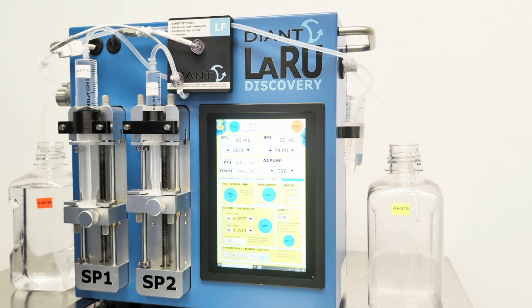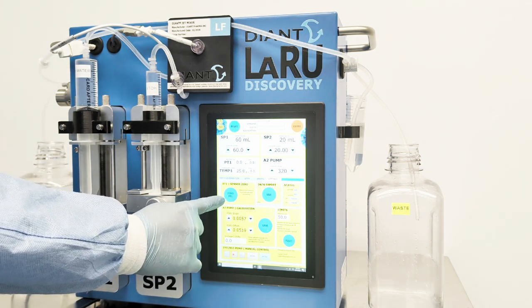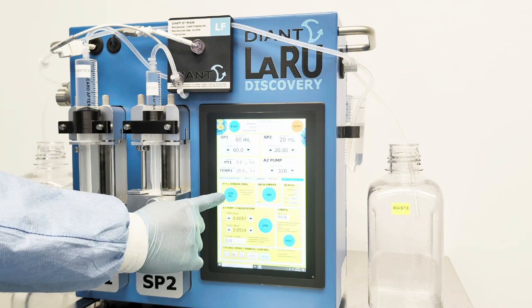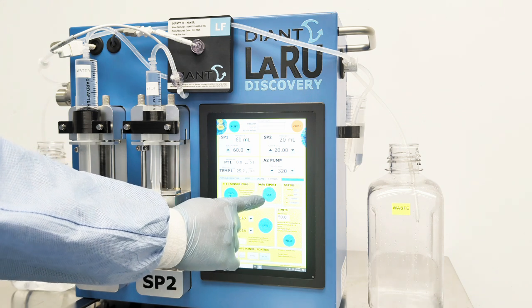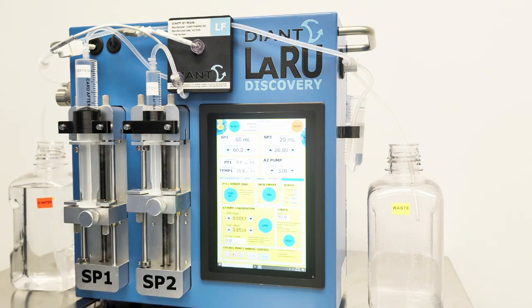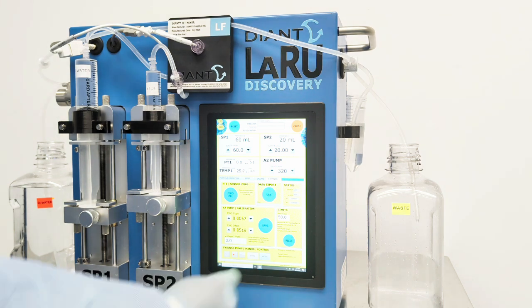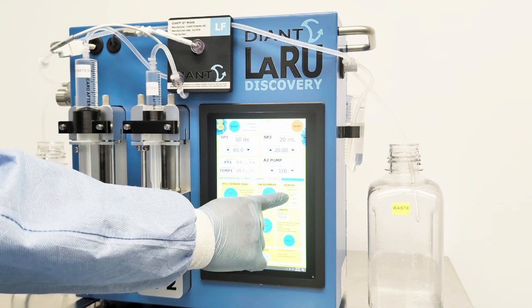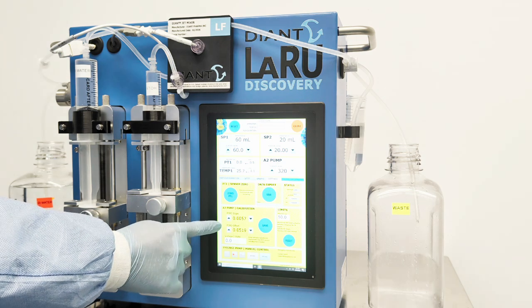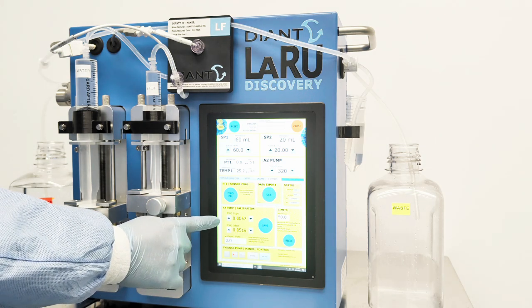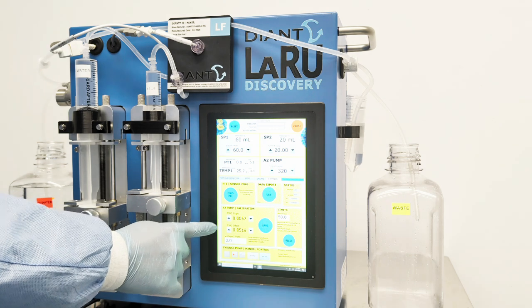There's also a Settings tab, and when you select the Settings tab, you have different options available. For example, the PT1 sensor 0, data export, status, A2 pump calibration, and limits. PT1 sensor 0 is used to zero out a new pressure transducer when connected to the system. It is important, when you add a new sensor, to zero the sensor prior to running. The data export button here will send all data to a USB that's connected onto the side of the system. Status is used more to indicate proper communication. The A2 pump calibration can be used, on occasion, for a calibration where we're just looking at a slope and offset to input based on the voltage that we observe.